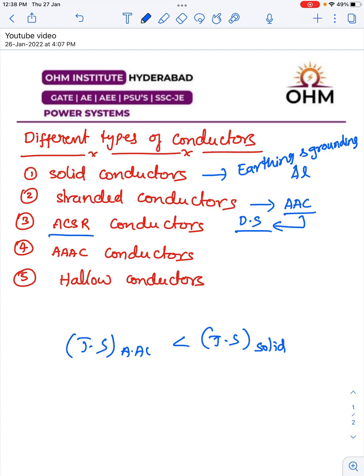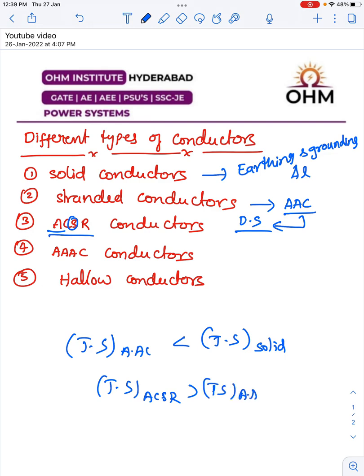Now, ACSR conductors. Since double AC conductors are not suitable for the transmission system, ACSR conductors came into the picture. Here, we use steel conductors in addition to aluminum conductors. A few strands are made up of steel and the remaining strands are made up of aluminum. The number of aluminum strands is more compared to steel strands, because the purpose of the steel strands is to increase tensile strength. So the tensile strength of ACSR conductors is greater than double AC conductors, and because of this improved tensile strength, ACSR conductors are suitable for longer spans and we can use them for the transmission system.